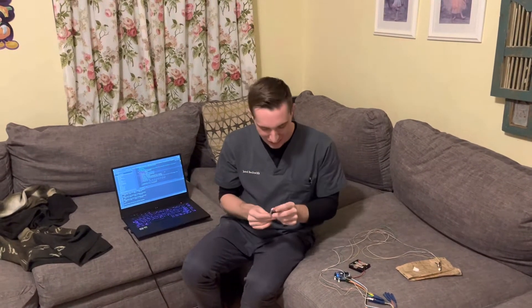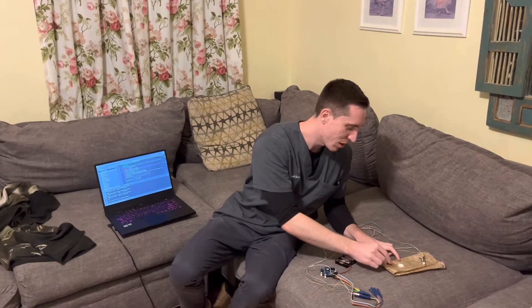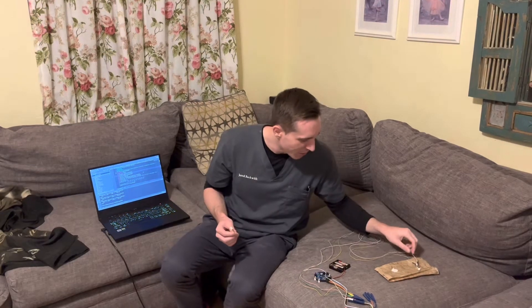We also have some prep — it's kind of like an exfoliating scrub that I will be using on my scalp to get low impedances so we get a good connection and a nice clean signal. You use this prep stuff to lower the impedances. You're gonna want to shoot for under ten thousand ohms — under five thousand ohms is perfect.